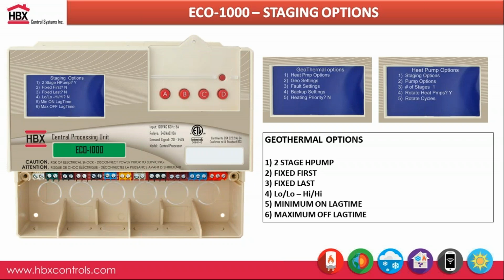We can have lead lag again with all our heat pumps. It's all based off of lag time, so you can adjust it from having that second or third heat pump fire up within 1 minute up to 240 minutes within the Eco 1000 as well. And you can also have a maximum off lag time as well. So how you want to stage these heat pumps when the demand is no longer there. So you may want them to go off a little bit longer than bring them up on.